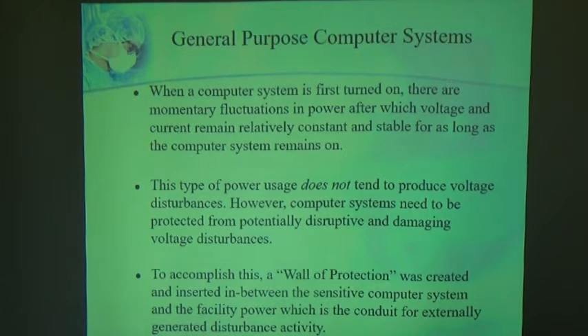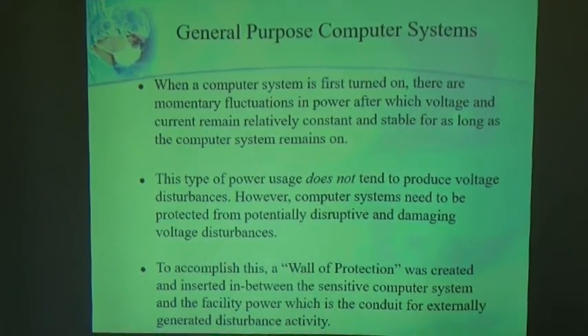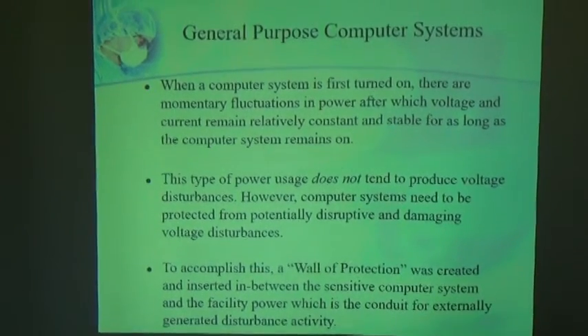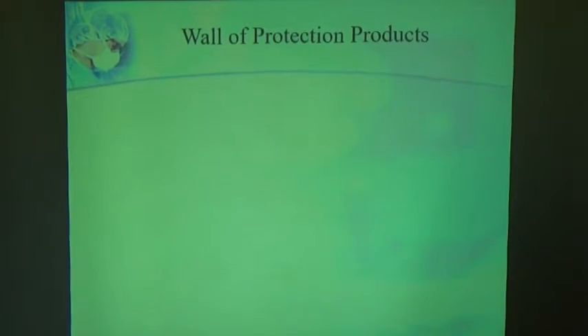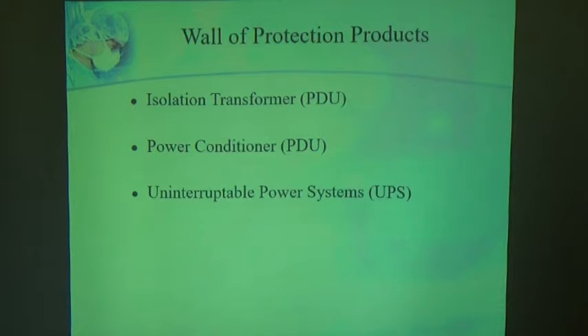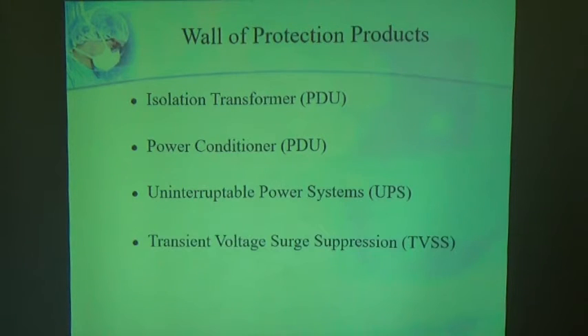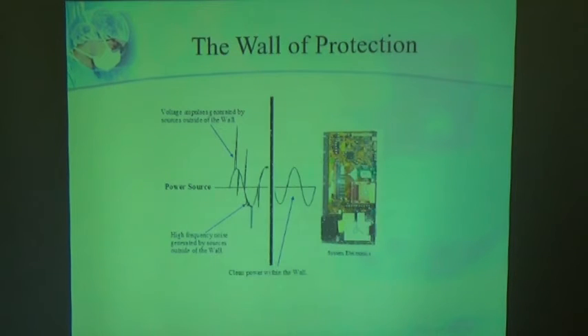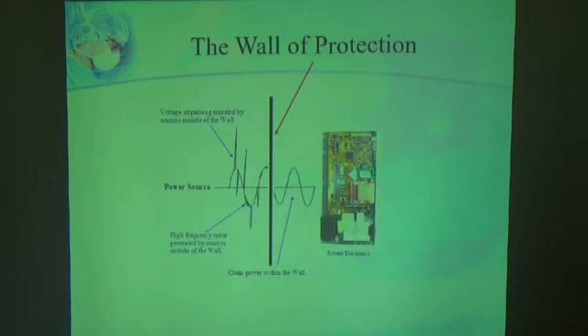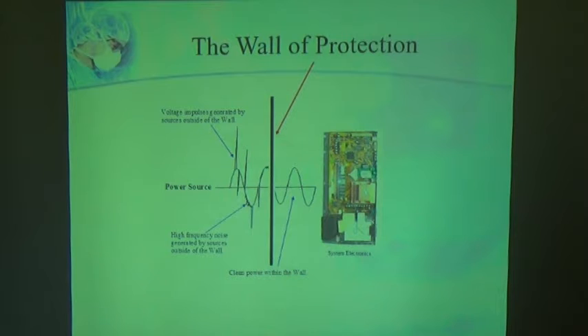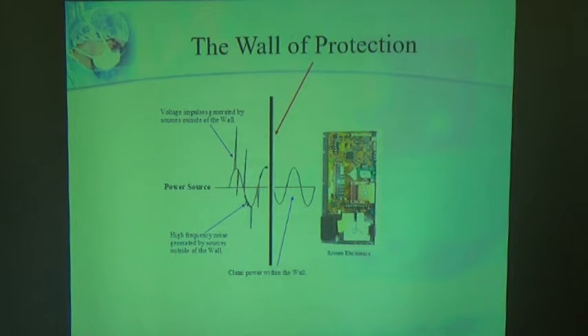To accomplish this, a wall of protection was created and inserted in between the sensitive computer system and the facility power, which is the conduit for externally generated disturbance activity. Wall of protection products included isolation transformer, power conditioner, uninterruptible power systems, and voltage transient surge suppression equipment. When looking at the wall, we can see on the left side of the graph, all of that disturbance activity is on the outside. The wall stands between that, and on the inside, feeding the sensitive electronic equipment, the sine wave is clean and all of the garbage is gone.